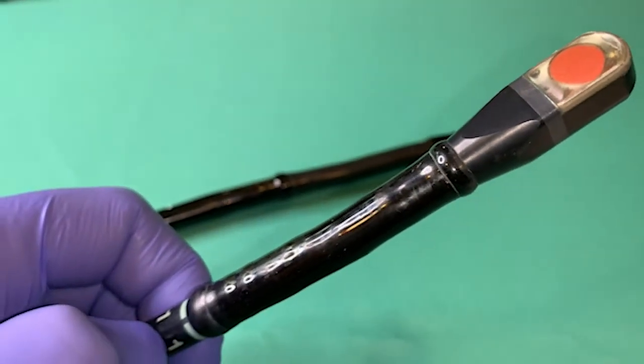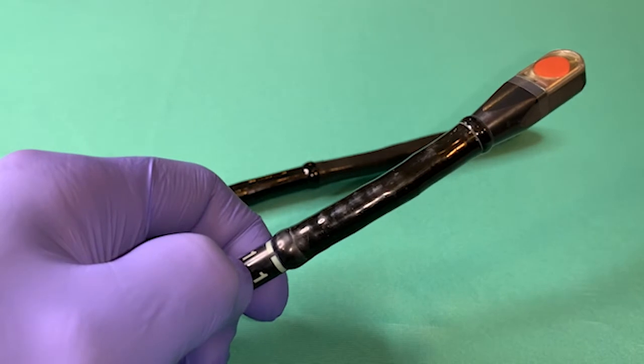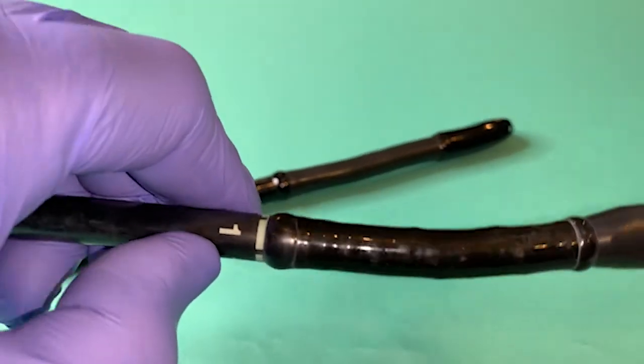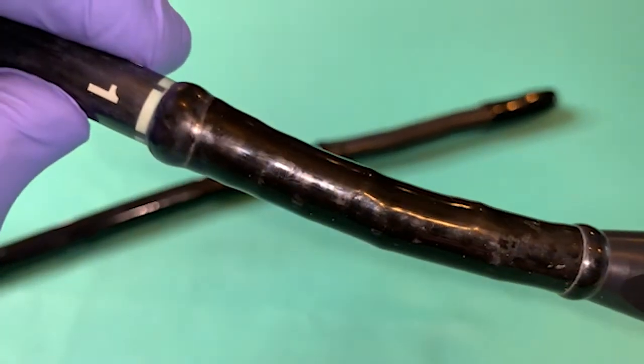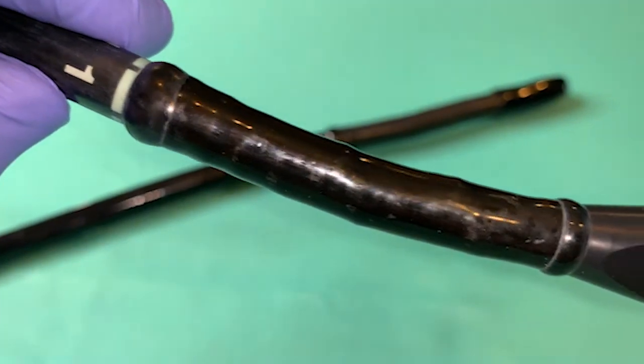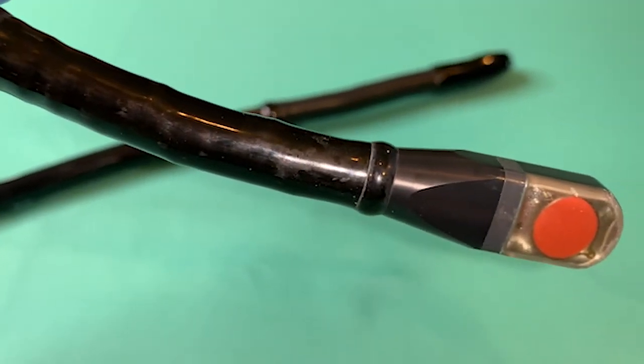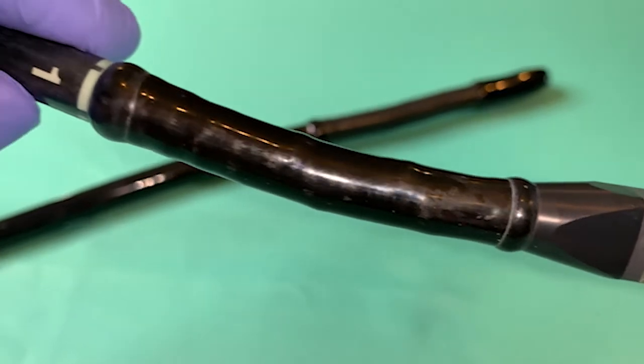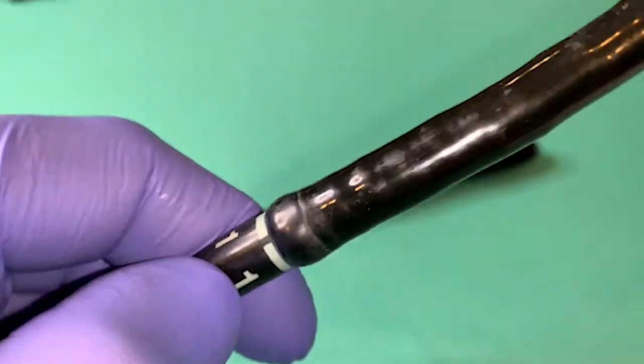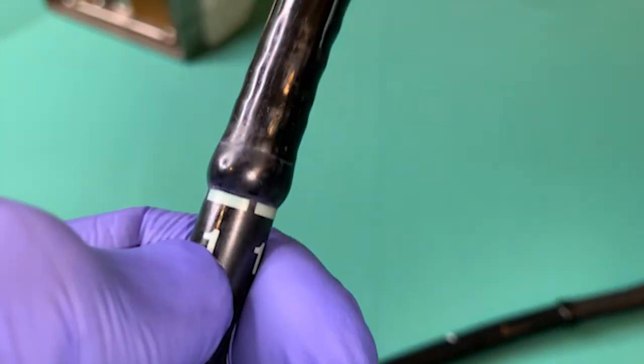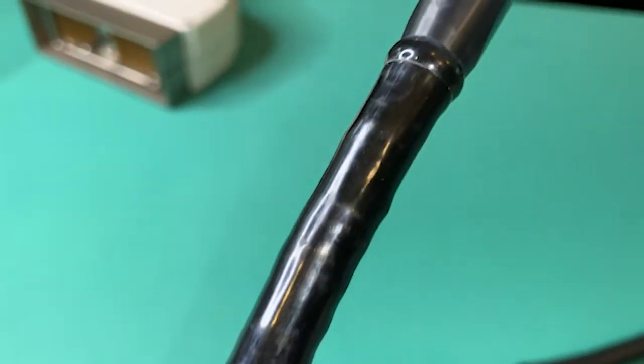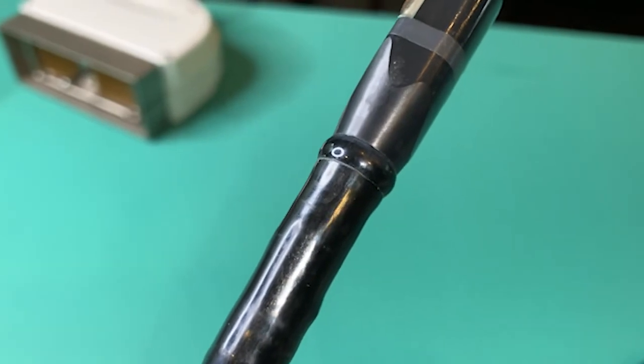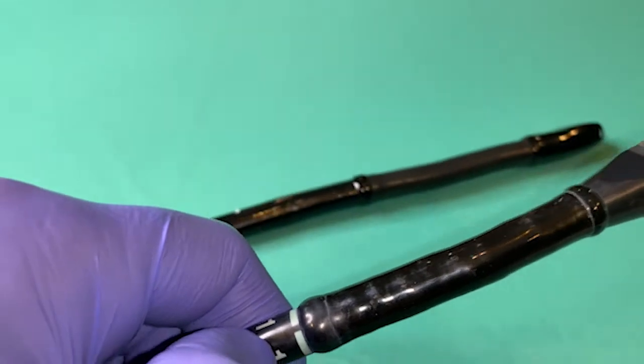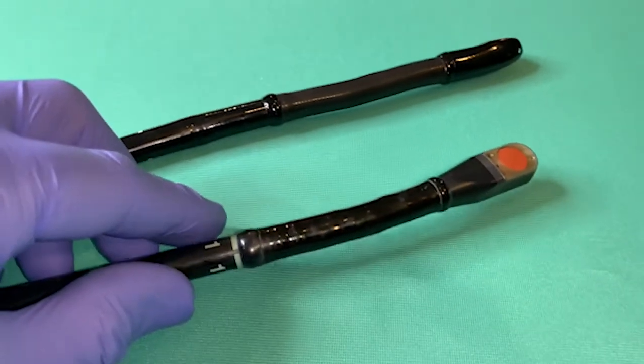Use a magnifying glass to closely examine the bending rubber for the appearance of any tiny pinholes, minor cuts, or abrasions. Inspect the adhesive glue beads on each end of the bending rubber, looking and feeling for evidence of impacts or any sharp edges. Examine the quality of the seals of the adhesive to each of the components, looking for any tiny voids or separations. Any area that is believed would allow fluid entry should be addressed with a high priority.